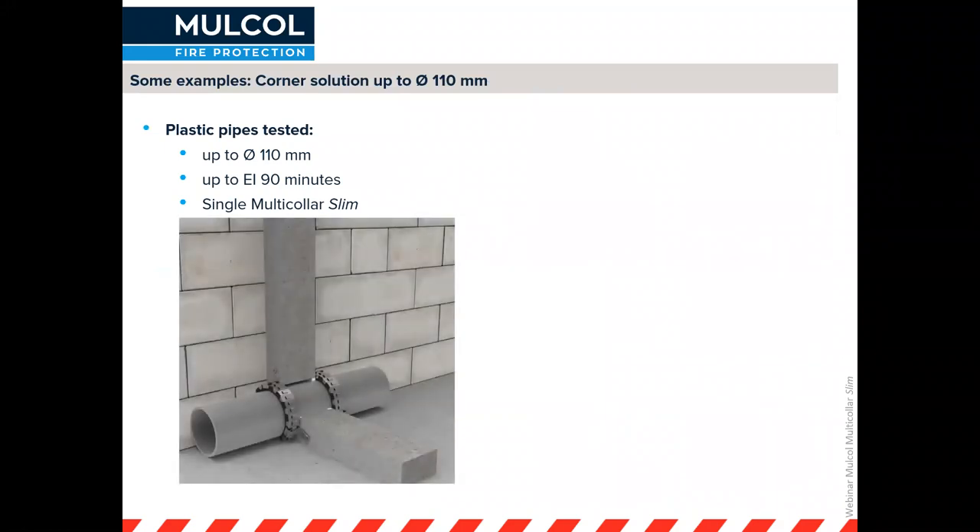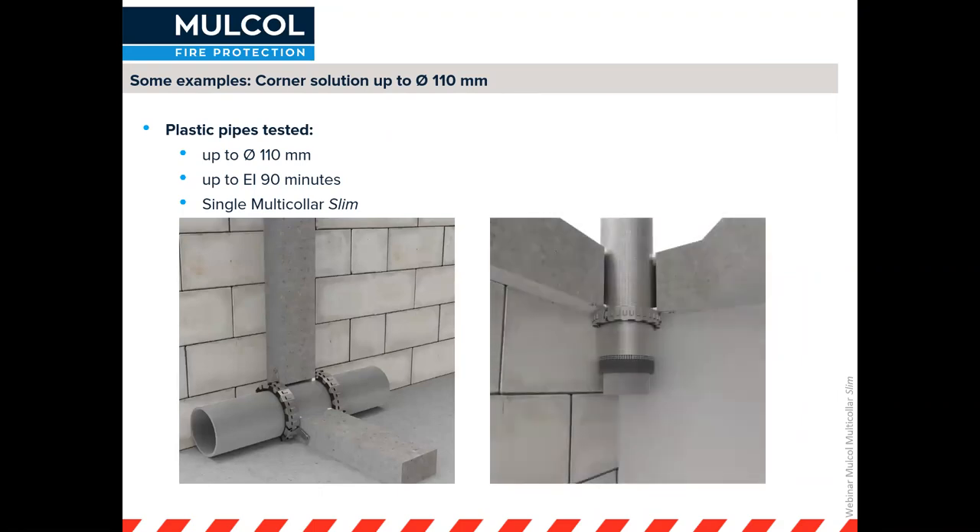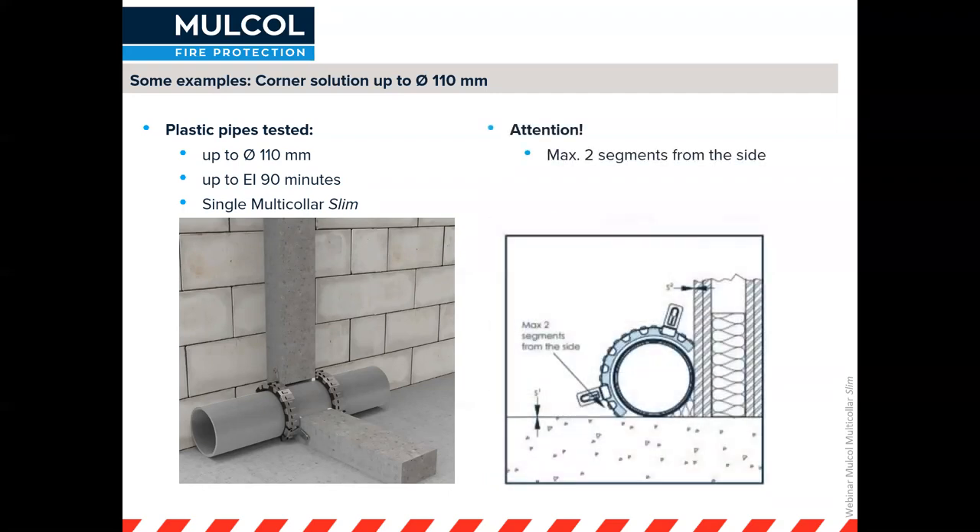For corner solutions, where you can't fit a collar physically all the way around, a single Multicollar Slim has been tested up to 90 minutes for both floor and wall applications. Something to pay attention to is that you have a maximum of two segments at the end of the clip, and the wall at the side and the floor need to be able to withstand the same fire rating.